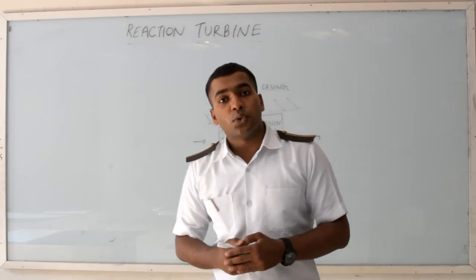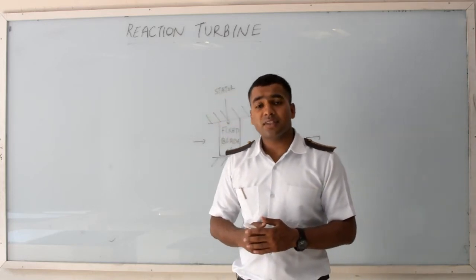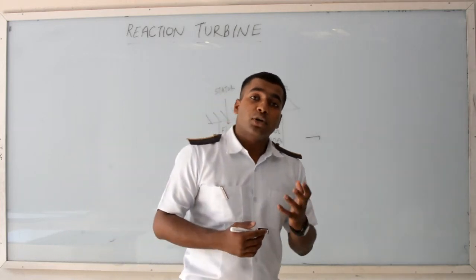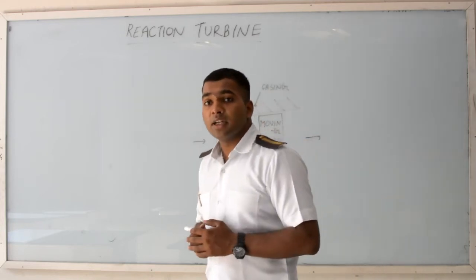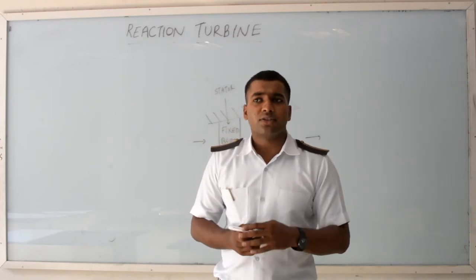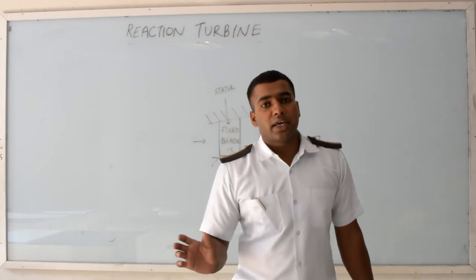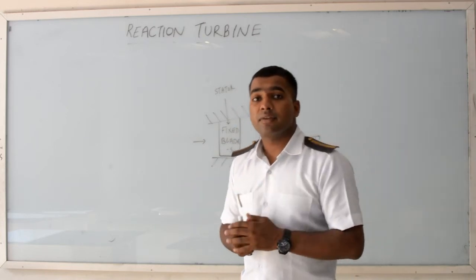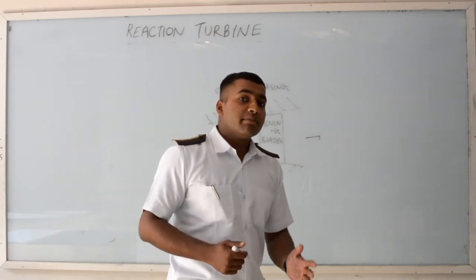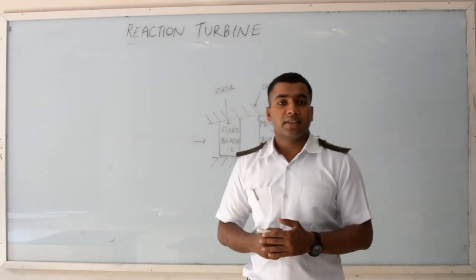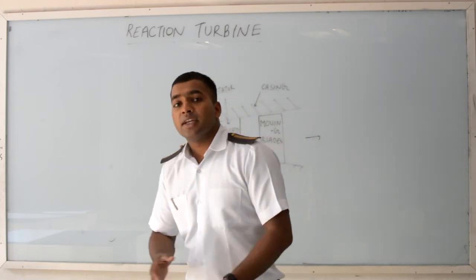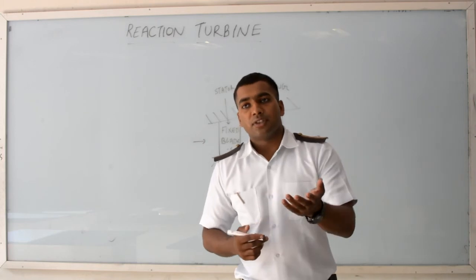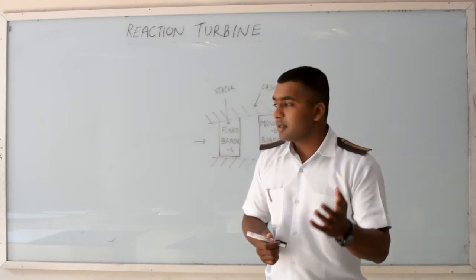I will now explain another parameter known as the degree of reaction. It is a mathematical parameter used to quantify how much enthalpy drop is taking place in the stationary blade and in the moving blade. Mathematically, it is the ratio of enthalpy drop in the moving blade divided by the total enthalpy drop in the stage. A 50% degree of reaction means there is an equal enthalpy drop taking place in the stationary blades as well as in the moving blades. A 0% degree of reaction means there is no enthalpy drop taking place in the moving blades — this is an example of an Impulse Turbine.